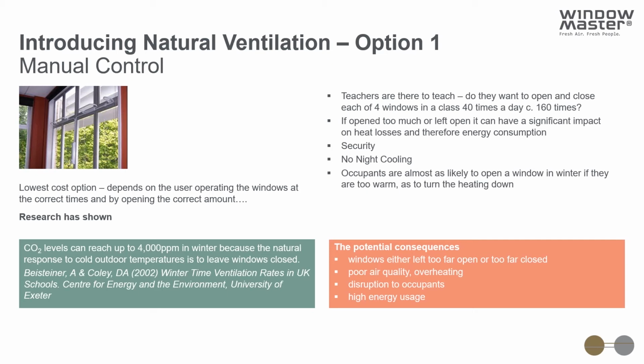There was a study done a few years ago which looked at a typical classroom. It looked at the thermal performance model, the CO2 requirements, and a typical weather model. It demonstrated that in order to hit the energy figures, thermal performance, and air quality, the windows would have to change position approximately 40 times a day. So if there were 4 windows in a room, that might be 160 operations of those windows in order to achieve all of the energy, comfort, and air quality figures.